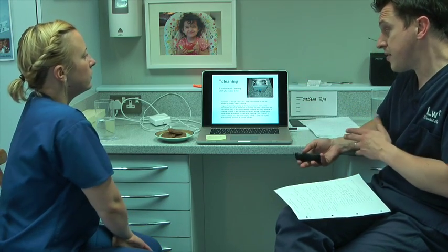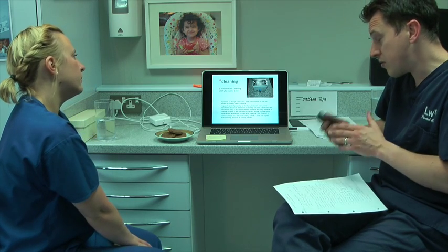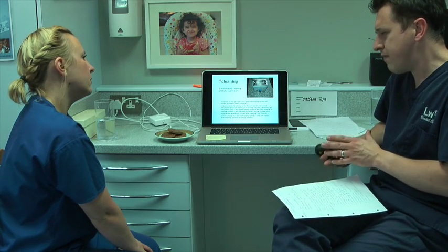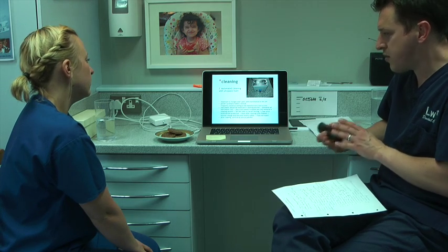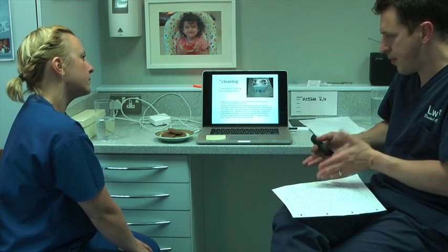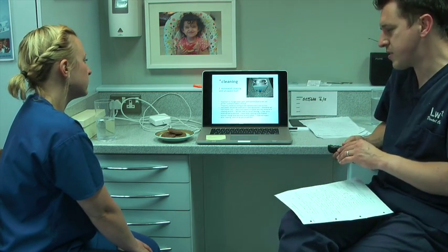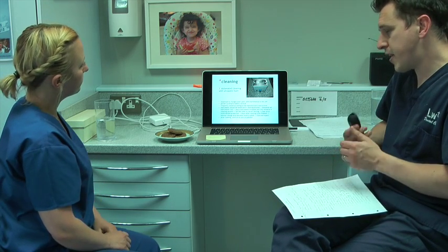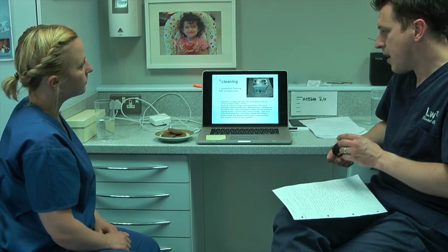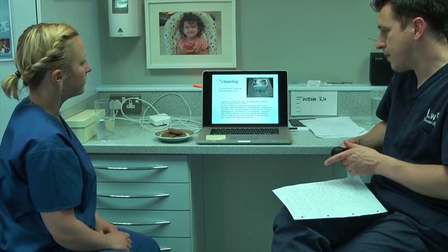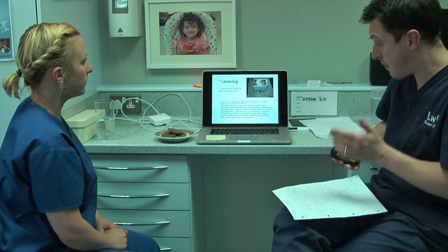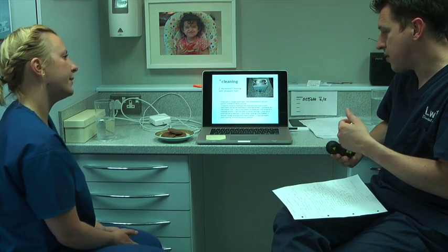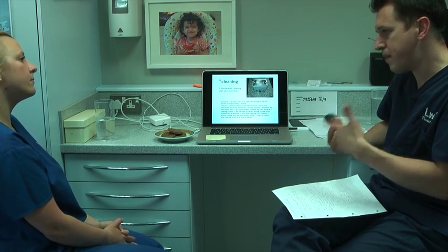Not as effective is the ultrasonic bath cleaning. You can validate this to a point, but it's not as concrete and belt and braces as, say, the washer disinfector is. It's really important to change the water and maintain the unit regularly. It's proven to enhance debris removal compared to manual cleaning.